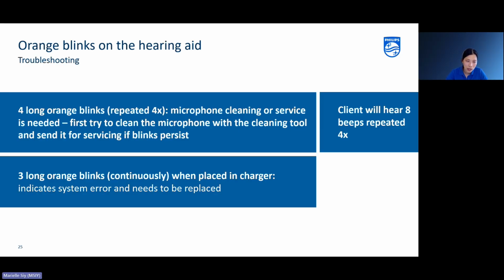In terms of the sound, the client will tell you that they hear 8 beeps repeated 4 times. This is a visual indicator and this is the audio indicator. If that's what you get from the client, then probably there's something wrong with the microphone or it needs to be cleaned. And if the LED shows 3 long orange blinks and it's very continuous and doesn't stop when placed in the charger, then there's something wrong with the hearing aid. It indicates a system error and the hearing aids need to be replaced. That's a serious kind of blink that you don't want to see. But hopefully that doesn't happen very often in your experience.